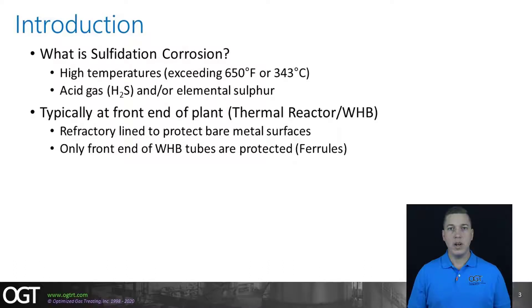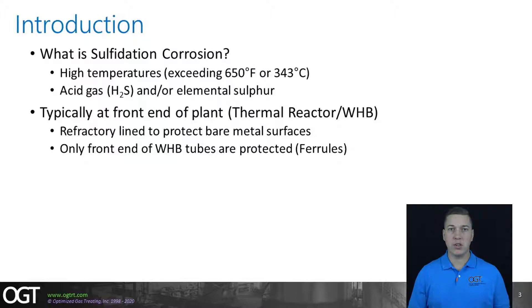What is sulfidation or sulfidic corrosion? The general description is high temperature attack of metal by acid gas, namely H2S. In most cases, this increased corrosion rate occurs at temperatures exceeding 650°F or 343 degrees Celsius.